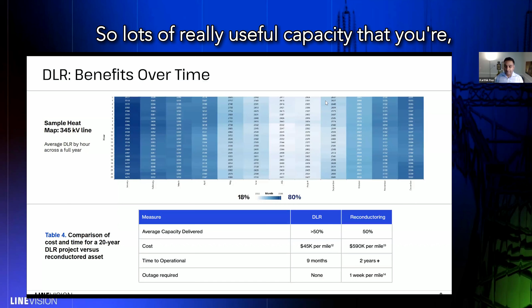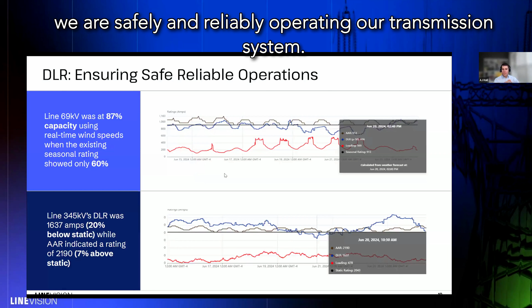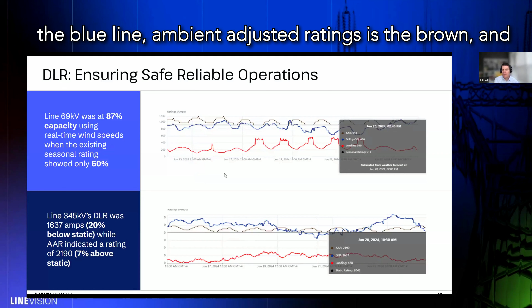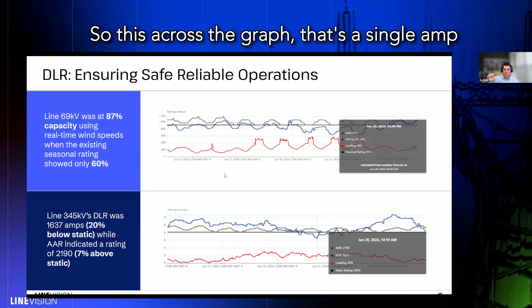All right, so I mentioned DLR is not just for capacity gains. And here we'll look at how DLR can ensure that we are safely and reliably operating our transmission system. I know the graph might be a little rough to see, but just to explain quickly, DLR on the graph on the right is the blue line. Ambient adjusted ratings is the brown, and then the static rating is the straight line. So across the graph, that's a single amp rating for the line, and the red line is the actual loading on the transmission line.